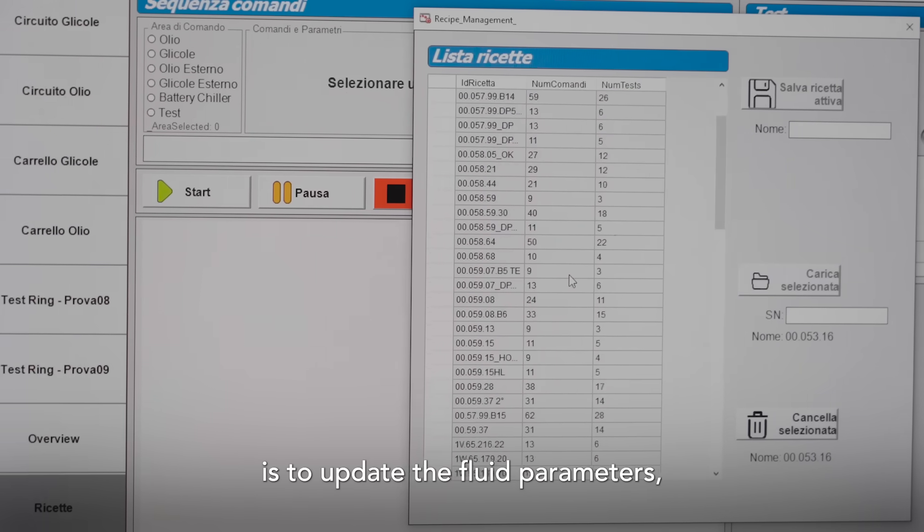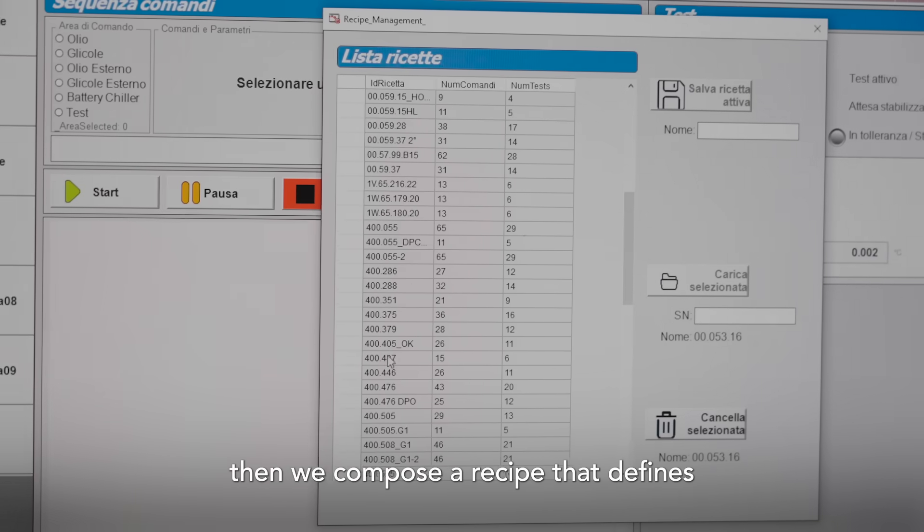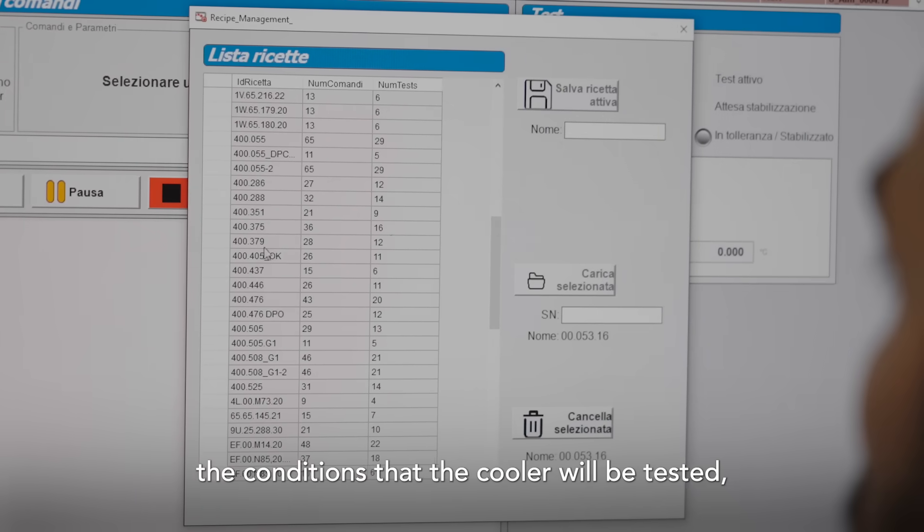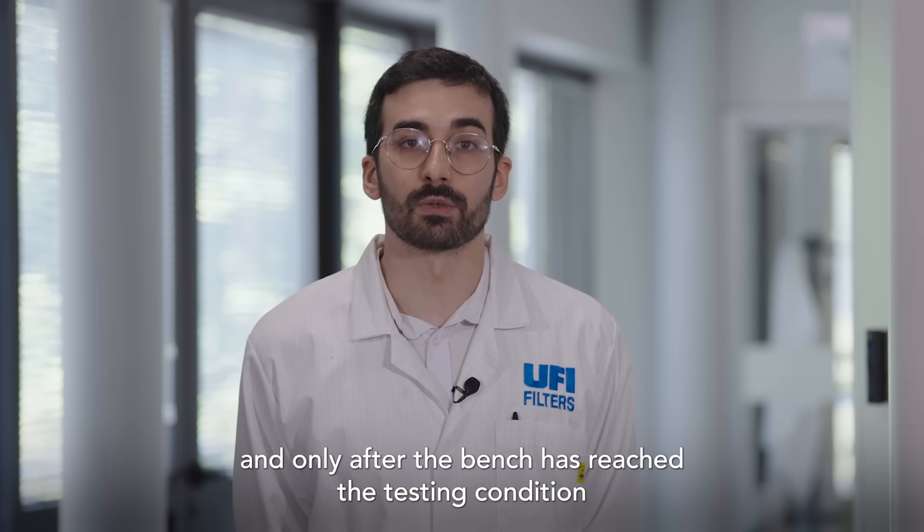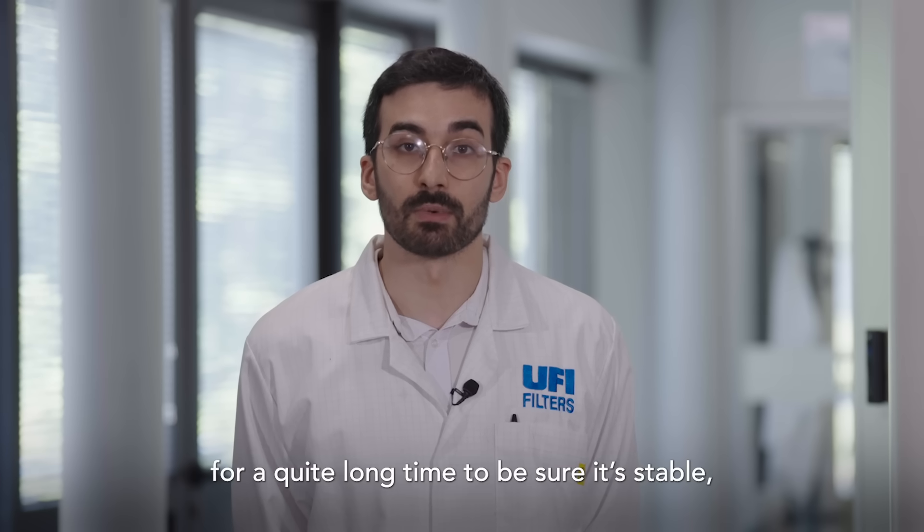When we test an oil cooler, the first thing we do is update the fluid parameters, then we compose recipes that define the conditions the cooler will be tested. Only after the bench has reached the testing condition for quite a long time to be sure it's stable, the test can start.